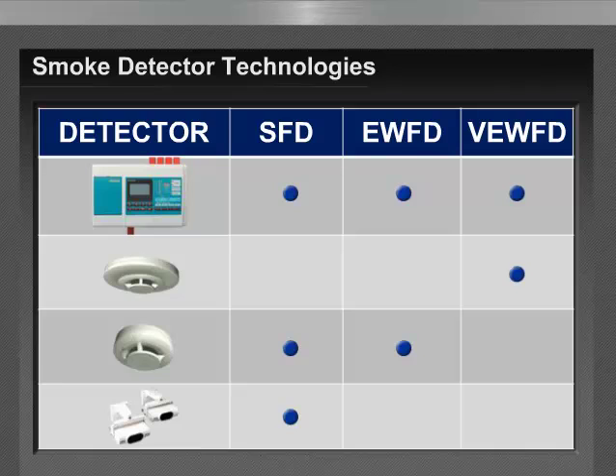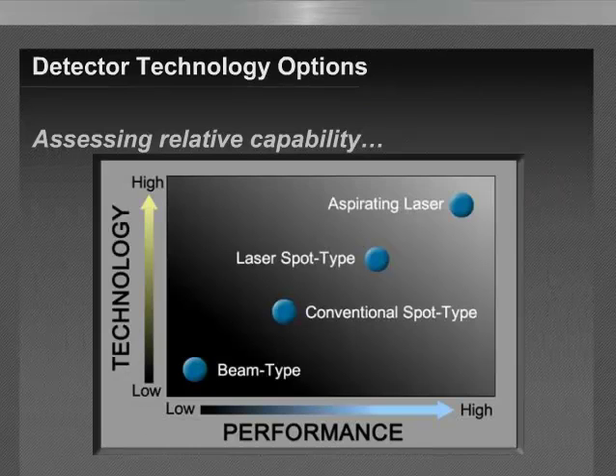And then the final on the list is aspirating laser-based smoke detection technologies. Now, we'll see that across the entire range: standard fire detection, early warning fire detection, and very early warning fire detection. And the reason for that is because of the sensitivity range of those specific technologies that allow its operation in each and every one of those sensitivity categories. And it's just a matter of spacing the sampling ports in such a manner that you achieve the desired sensitivity category, if you would. All right, so selection is based on the technology's suitability to effectively perform its intended function within the sensitivity objectives.